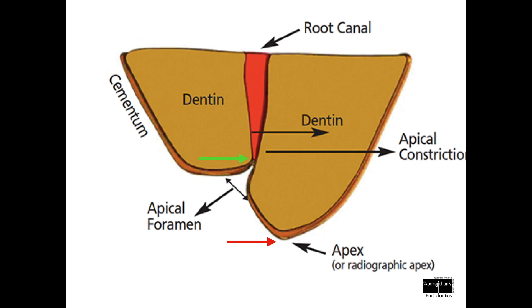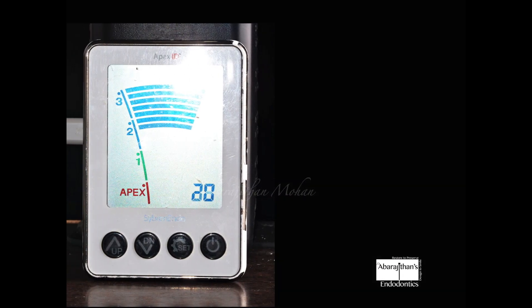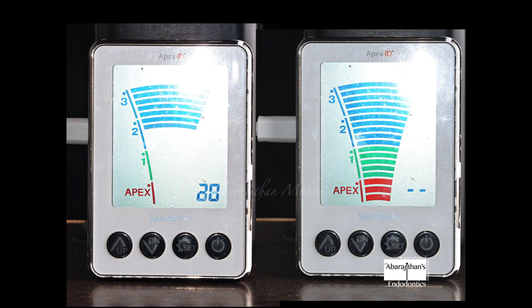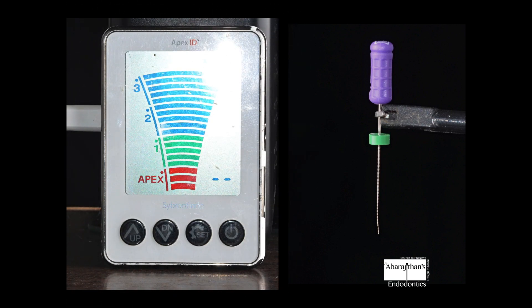The right way of determining where exactly the pulp tissue ends, or where the apical constriction is located, is mainly by the advent of apex locators. Apex locators are simple electronic devices — they have two electrodes. One electrode is the lip clip which is attached to the patient's lip, whereas the other is the file holder, traditionally used with K-files. By slowly moving the K-file inside the root canal, we see the visual display on the apex locator, which is used for determining the working length.